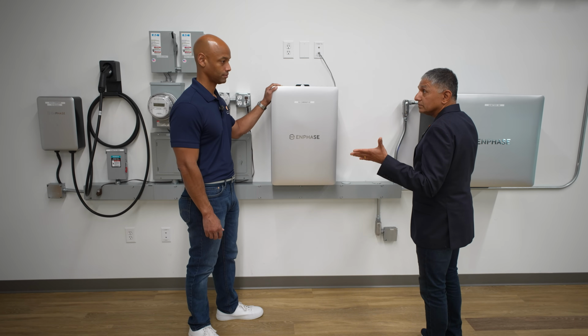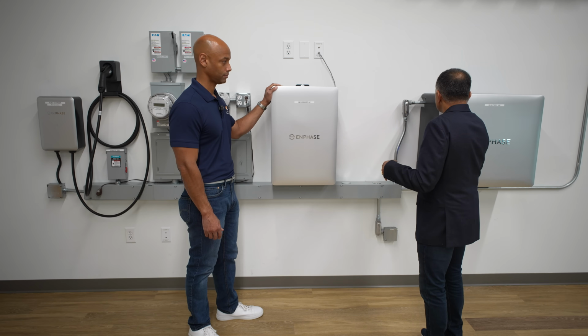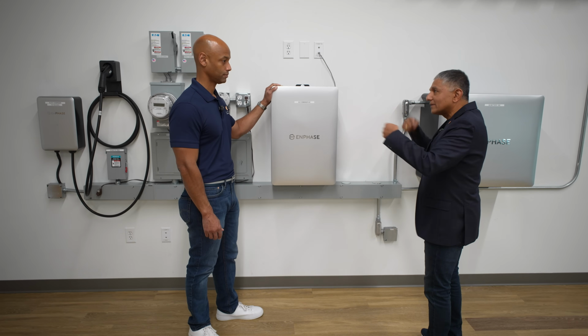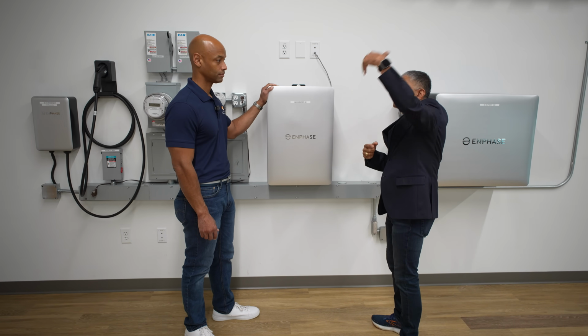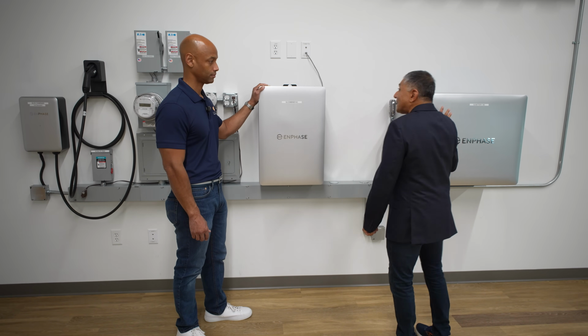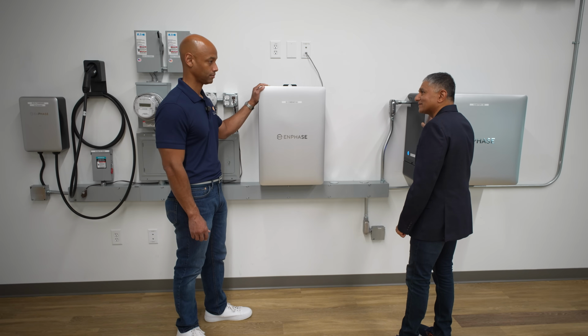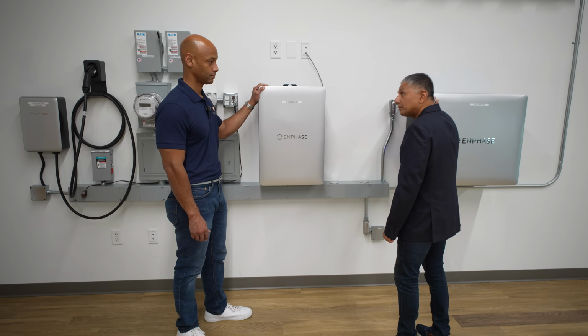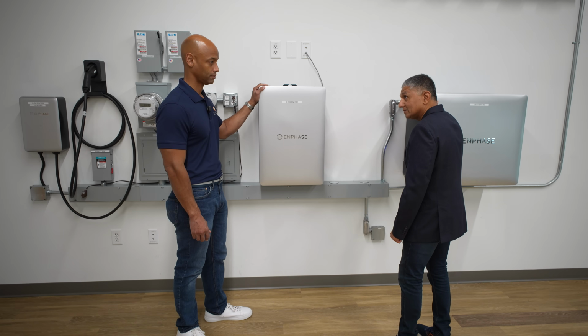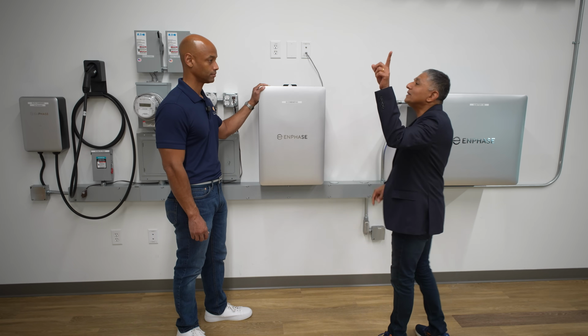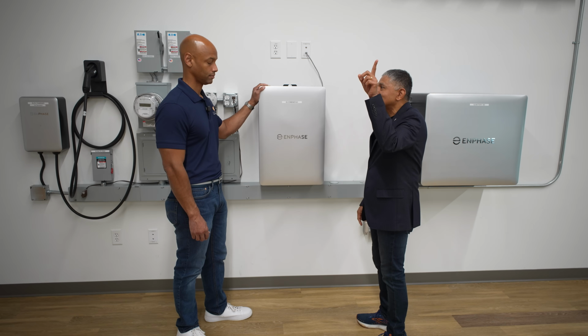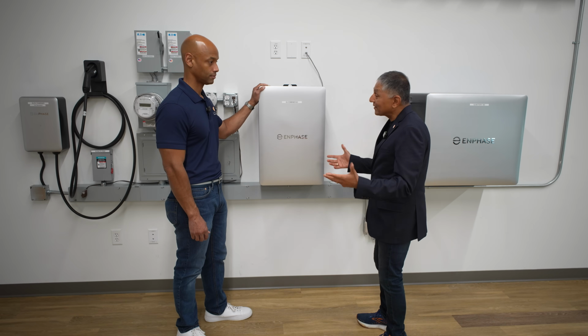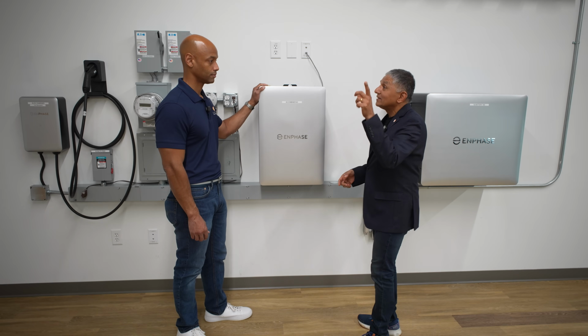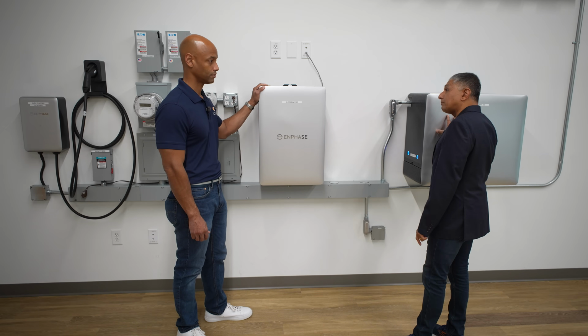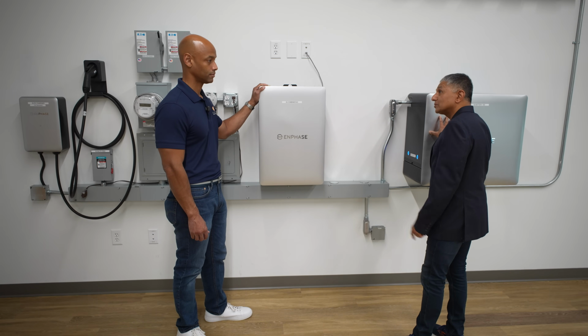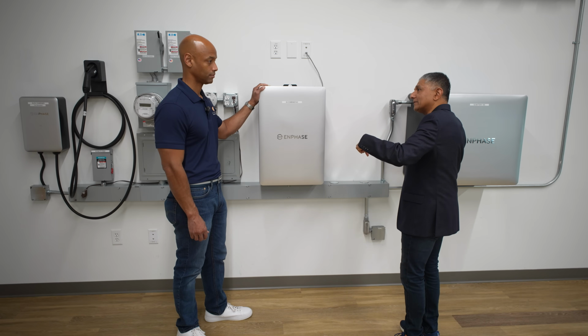In a typical system, what would happen is the battery synthesizes the grid, and then the PV says, oh, I see a grid, and connects to it. So the battery has to be the first one to synthesize the grid. If the battery is not capable of synthesizing a grid in an outage, PV never starts up even though the sun is shining. But with Enphase, if you have an IQ8 on the roof, the IQ8 synthesizes a grid independent of the battery. So the IQ8 can start charging the battery.